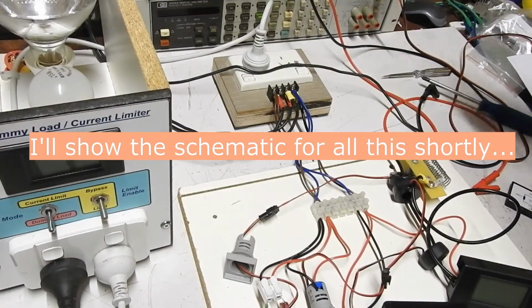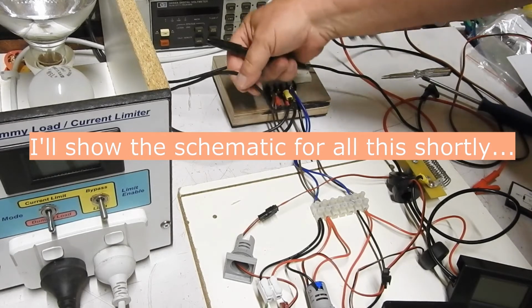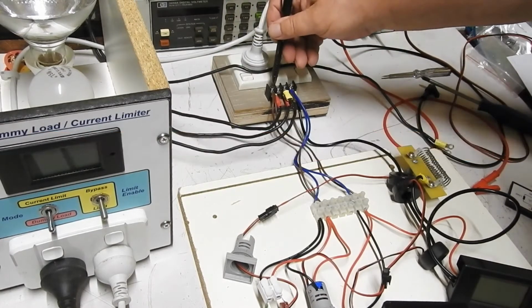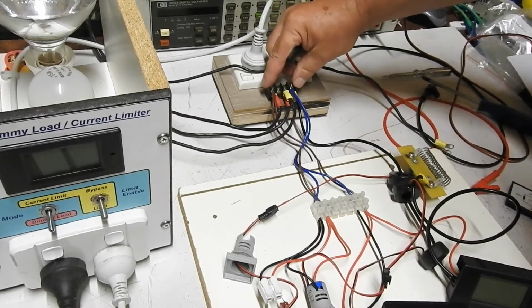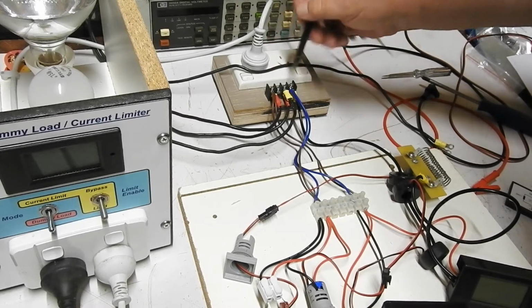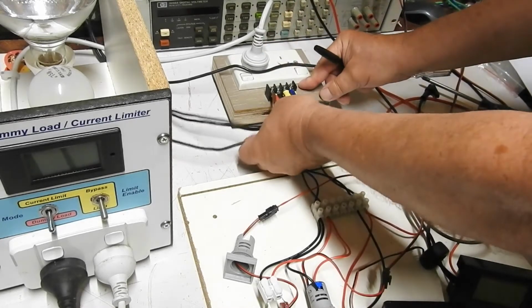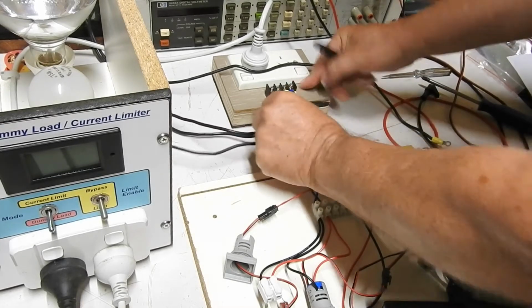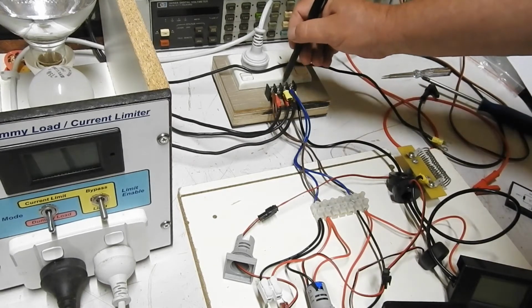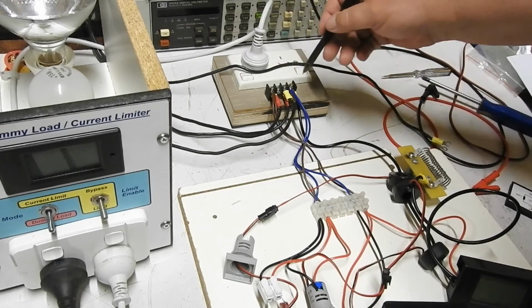One side of the transformers goes to this terminal. The two outside terminals on this go to the power point. The middle two do nothing, so these two are just a junction between the two transformers, effectively the centre tap of the combined transformers.